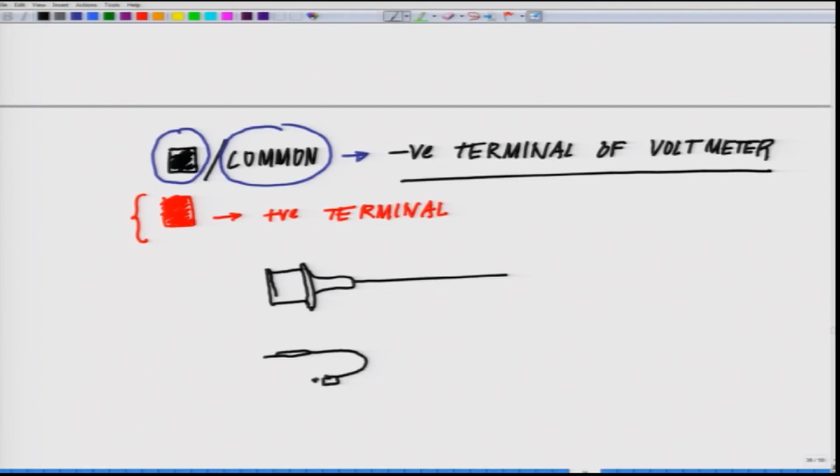If you look at the pH meter very carefully, you will see a socket, or a thin connector like this. The positive terminal is at the center, inside the connector. So, in other words, here your positive is out here at the center, and this rim is where the negative is. So, try to realize, if sometime you want to do some kind of a trick, the center is the positive and the outer periphery is the negative.